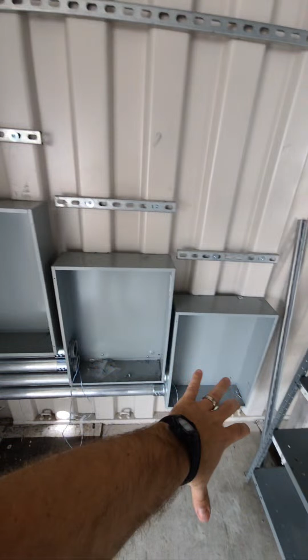More wire, and he's got these boxes. I'm not the electrician here, but if I remember correctly, these are where the big wire comes in. There'll be some disconnects and stuff, and then it'll be wired into the PDU. So the PDU wires will be 13 going up into the tray, and 13 going to the PDU, which is right here, and the PDU is going to be on each of these legs. So wire comes through the tray, goes straight into the PDU, and the PDU will be straight up and down right here.